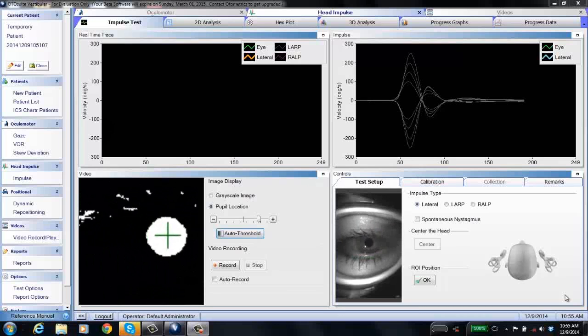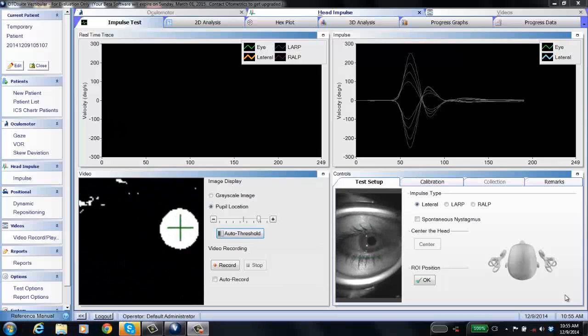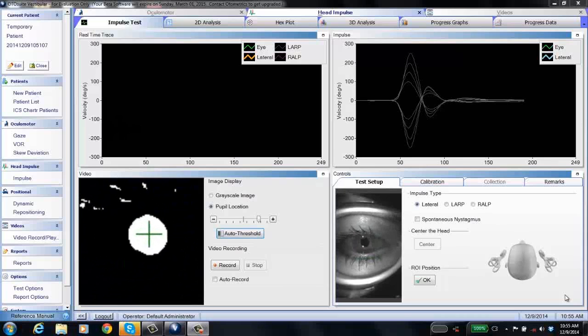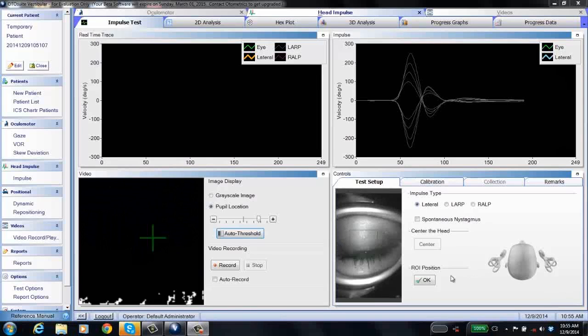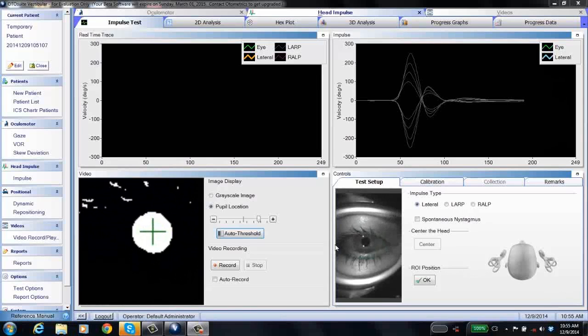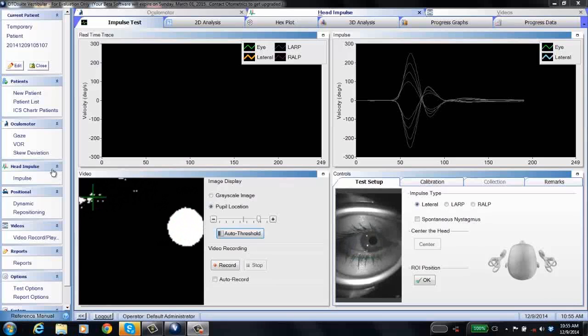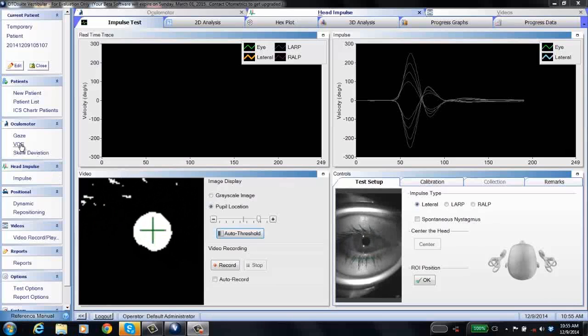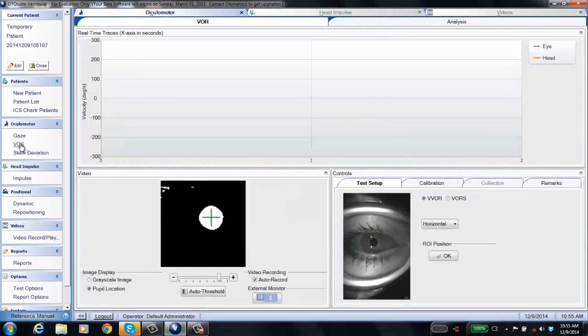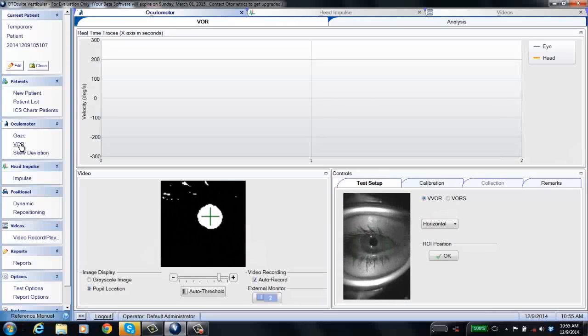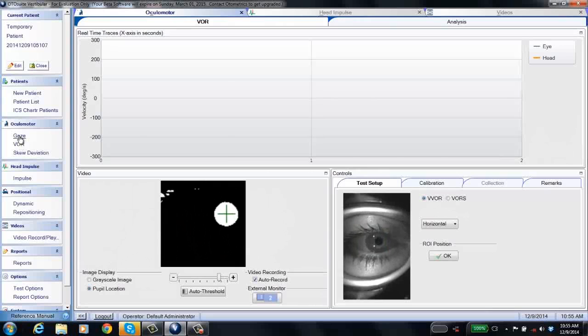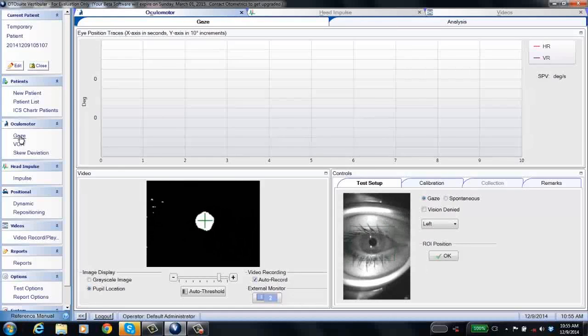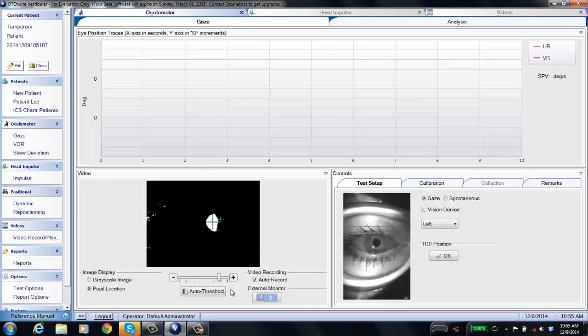The pupil detection for VHIT and VOR are very similar and I'll show you the difference with all the other tests. So for VHIT and VOR, you have a region of interest box that's 100 by 100 pixels. And here's the VOR. And that's because we're collecting the data at 250 frames per second. When we go to the other test, we'll go to gaze here, you have a box that is 160 by 120.